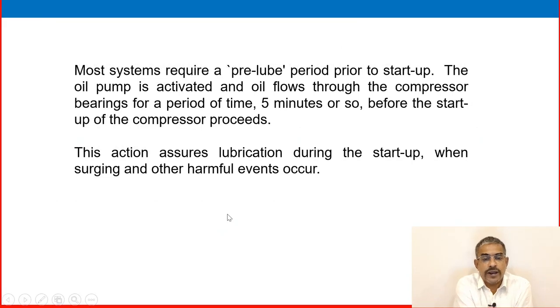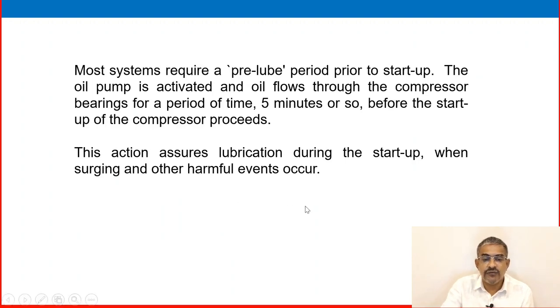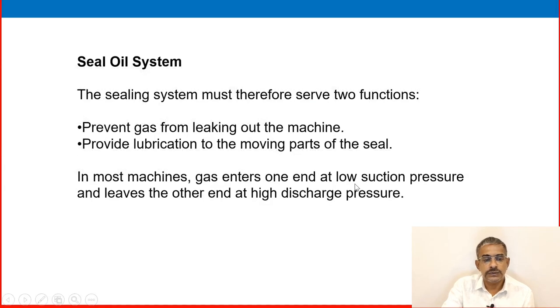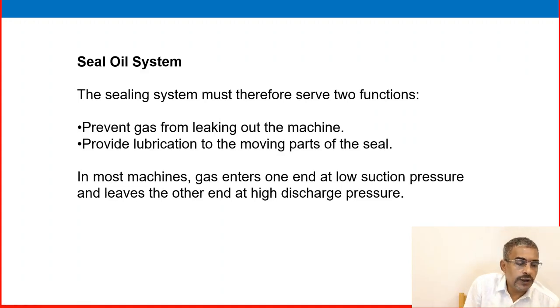Most systems require a pre-lube period prior to startup. The oil pump is activated and oil flows through the compressor bearings for a period of time — about five minutes — before the compressor startup proceeds. This assures lubrication during startup when surging and other harmful events can occur.